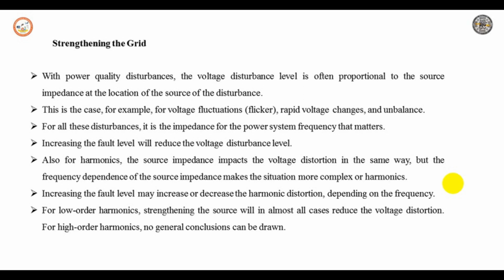Also for harmonics, the source impedance impacts the voltage distortion, but the impedance depends upon the frequency. That makes the situation more complicated for harmonics. An increase in the fault level may increase or decrease the harmonic distortion depending upon the frequency. For low order harmonics, strengthening the source will in almost all cases reduce the voltage distortion. For higher order harmonics, no general conclusion can be drawn.